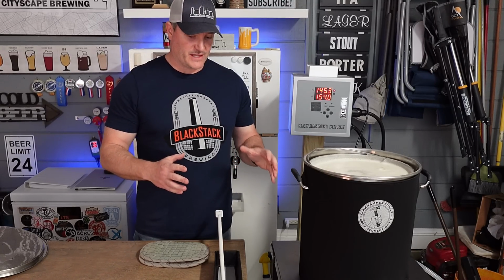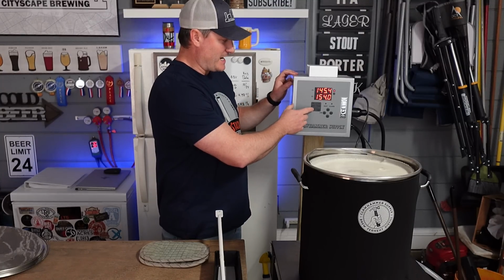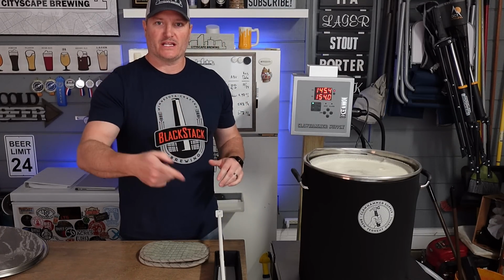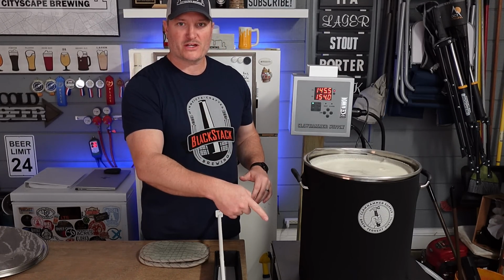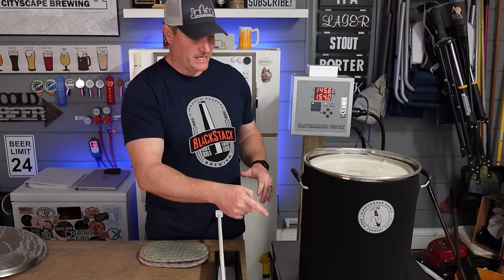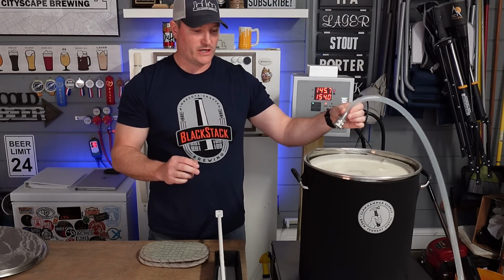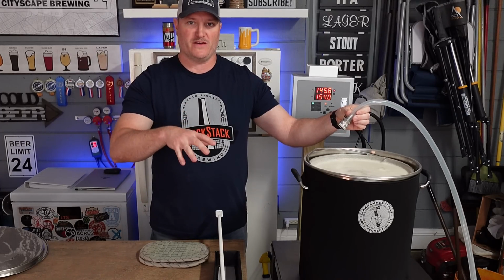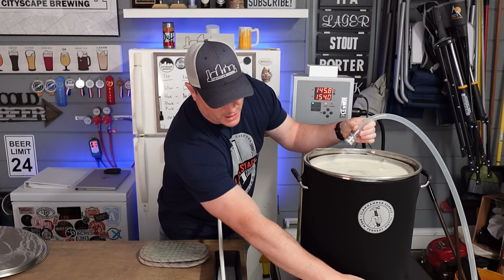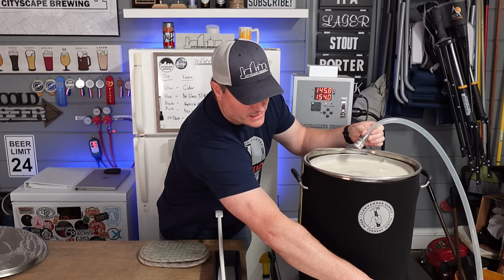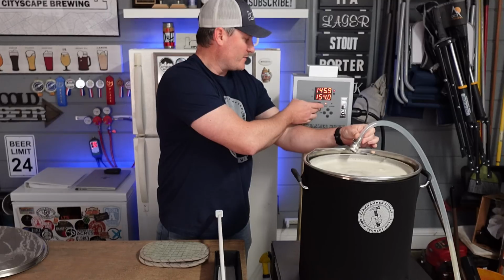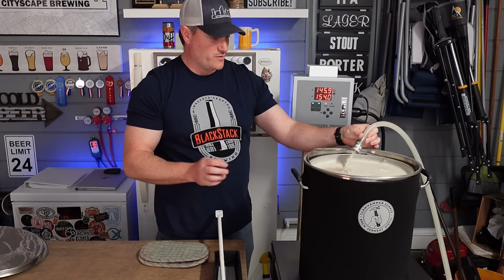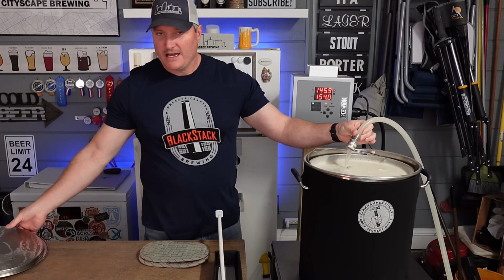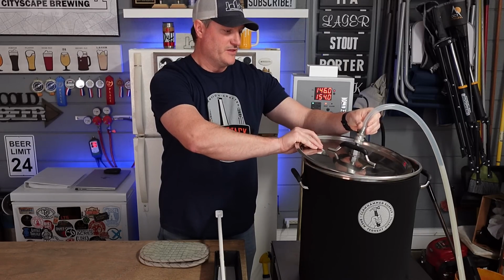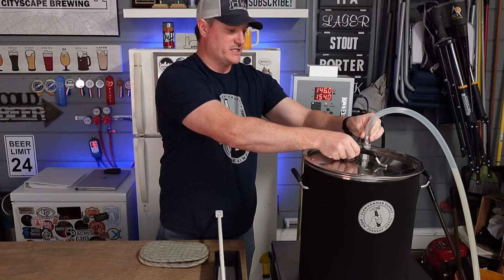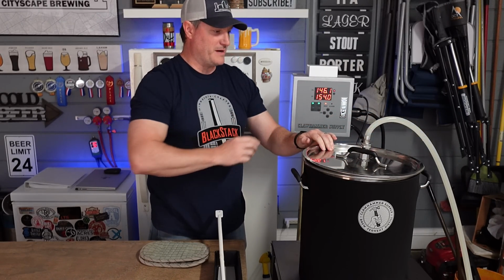Now that we've got everything good and mixed in, we can turn this back on to the heat and recirculate using that pump. Make sure your valve on the pump is turned on. You're also going to want to take your hose, get it started in here, and hook it up to the lid, which has a spray valve on top. So open up the valve in front, let that circulate down, turn on the pump, let it start going, then turn it off, and hook it onto the lid. This helps it get started and prevents air bubbles, then turn it back on.